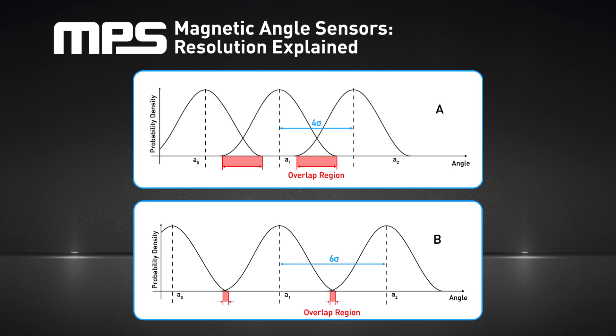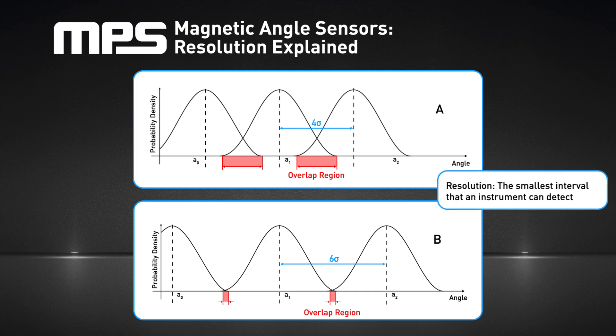The US National Institute of Standards and Technology defines resolution as the ability of the measurement system to detect and faithfully indicate small changes in the characteristic of the measurement result. Resolution is then the smallest interval that an instrument can detect. To determine this interval, we will assume that the distribution of random errors follows the Gaussian distribution.